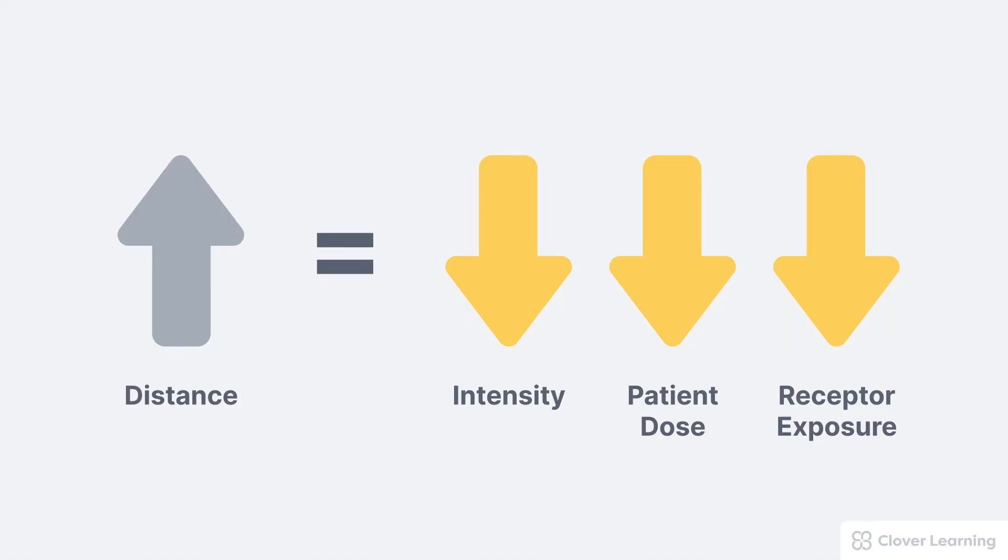Of course, the opposite is also true. If we decrease the distance—in other words, if we move the X-ray tube closer to the patient—the intensity at the patient increases, the patient dose increases, and the receptor exposure increases.